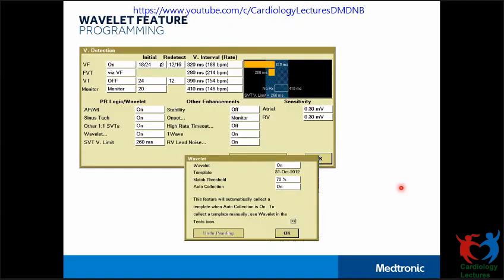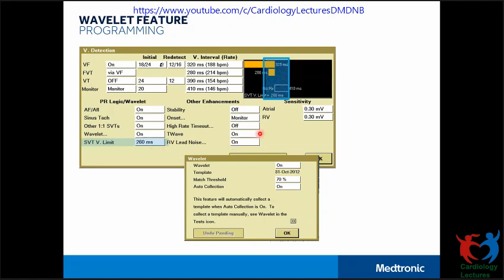On the programmer screen we can see the Wavelet feature. Clicking on it opens the next window where you can program the match threshold, which is nominally set at 70 percent. These templates can be collected automatically by the device or we can create one manually. Specifically for CRTD patients, we prefer doing a manual template collection. The SVT limit represents that Wavelet will be applied up to any rhythm above 260 milliseconds; if the rate is faster than this, Wavelet will not be applied.